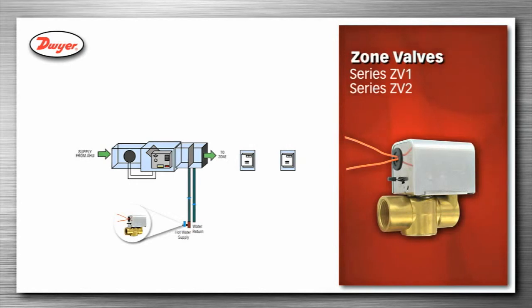VAV systems can include heating coils of hot water that the air flows past to heat the air up. Zone valves, series ZV1 or ZV2, are used to change the amount of hot water added to the heating coil, changing the air temperature.